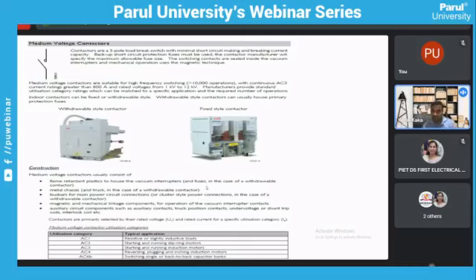Medium voltage contactors are suitable for high switching frequency. As we all know, some industries require frequent start-stop activity, so the number of switchings will be quite high. The limitation of applying breakers in this region is because of their endurance class, as well as the permissible number of switching operations a breaker is allowed, which is tested for around 10,000 operations. So whenever you exceed that or require frequent start-stop activities along the motor circuit, that is where contactors are used in the application.